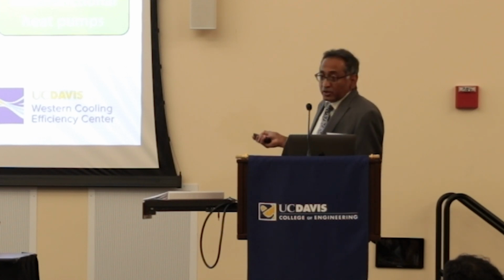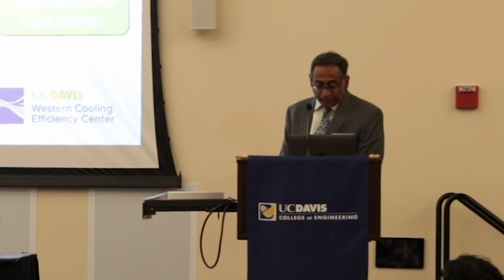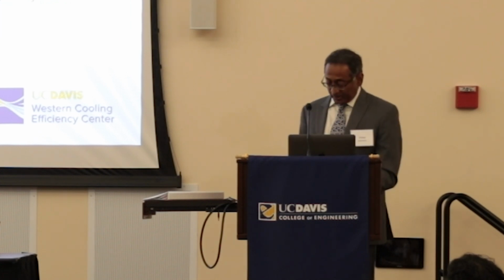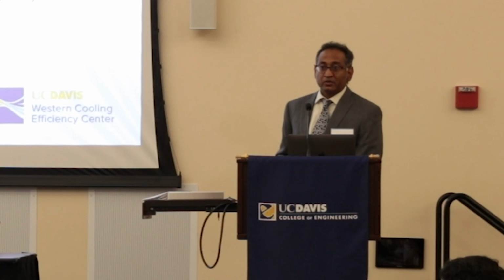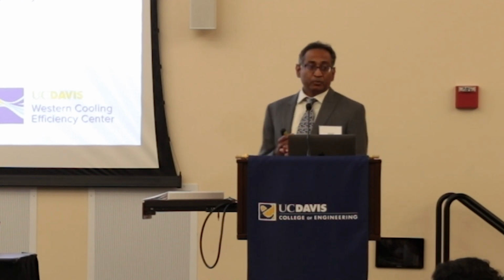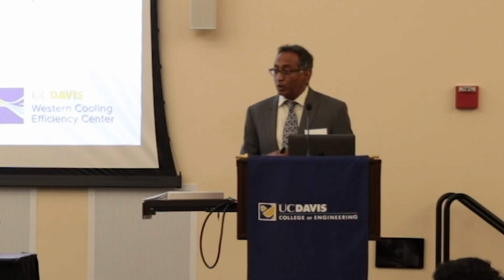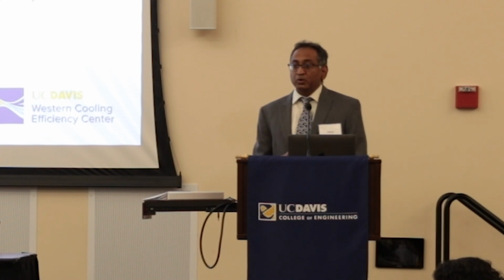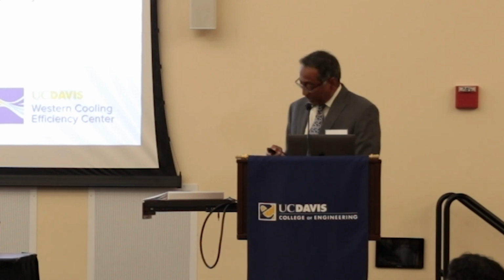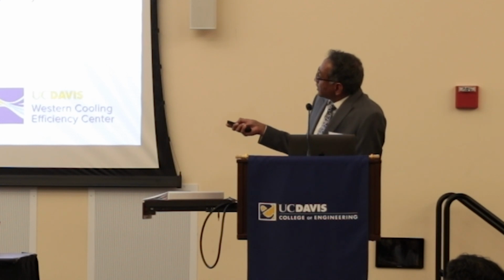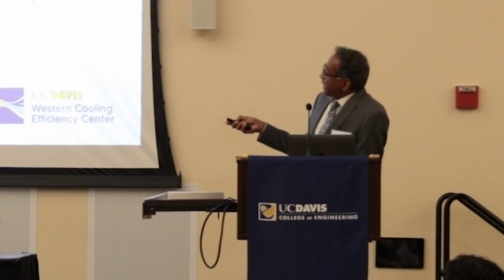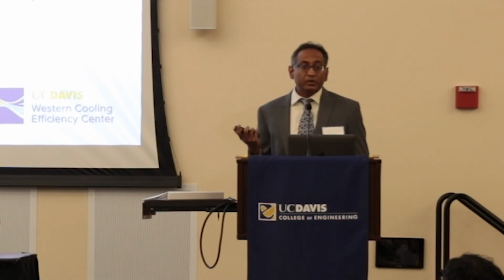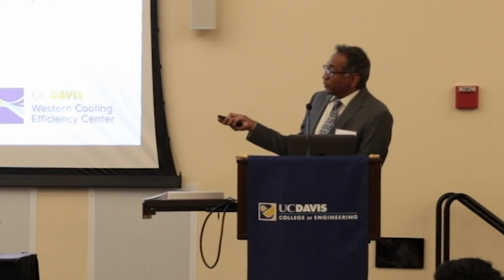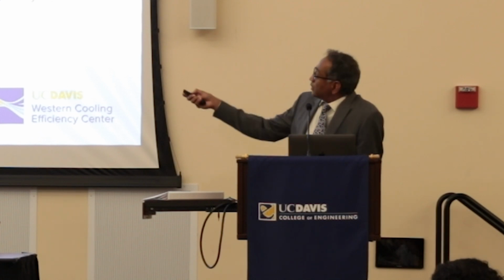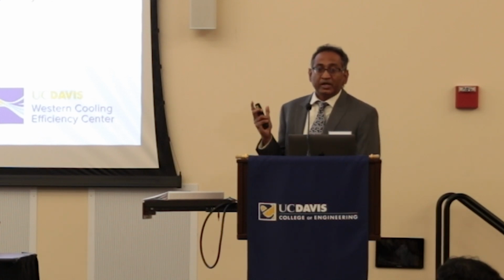But I'll focus on one potential technological solution, which is a multifunctional heat pump. The idea is, can you have one device that does everything? It does heating and cooling of the space, as well as water heating. And can that device help you get rid of that panel capacity problem? A multifunctional heat pump works like a traditional heat pump for space conditioning, but it also does water heating. And since the water heater tank is like thermal storage, you can rely on that for defrosting rather than putting strip heating with the air handler. So that's the basic idea behind it.